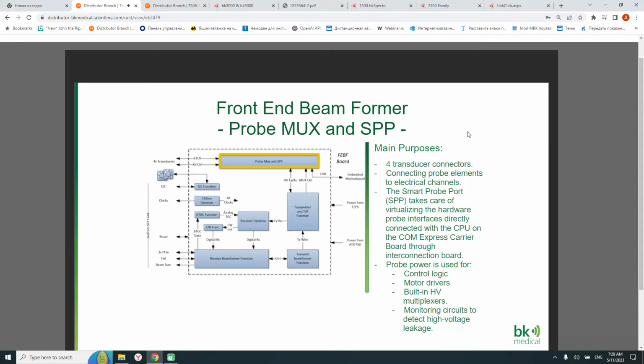The Smart Probe port, also called SPP, comprises a controller which takes care of virtualizing the hardware probe interfaces. This controller communicates directly with the CPU on the COM Express carrier board via the interconnection board. The probe mux and SPP function further provides power switches to apply power to any active probe. Probe power is used for control logic, for motor drivers, and for built-in high-voltage multiplexers. It also provides monitoring of circuits to detect high-voltage leakage to the connector pins.